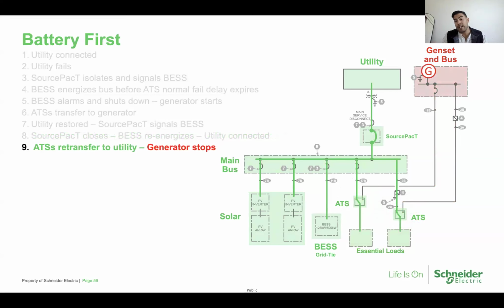And this is the ideal scenario where you're designing a microgrid system with PV. You want to use the battery first for emergency power. Again, these energy storage systems can be sized to provide at least 2 hours of runtime. And if you have transfer switches there, you can provide the energy storage system to provide power to those legally required NEC 700, 701 loads throughout your system, with the generator as a secondary emergency power resource should that energy storage system or outage last longer than 3, 4, 5 hours.